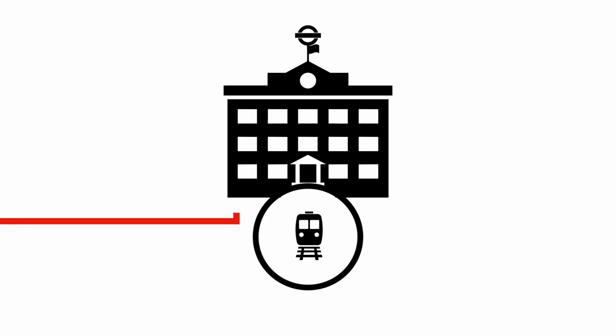Most busy stations will have at least 2 electrical intakes, with at least one being from the DNO and one from the 22 kV network, which is called the LUL supply. So if the DNO supply is disrupted, then we still have the LUL supply, right?